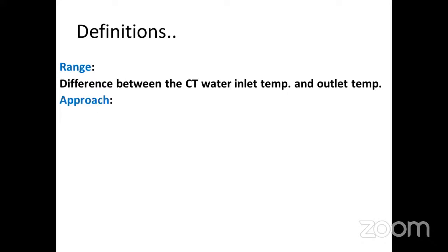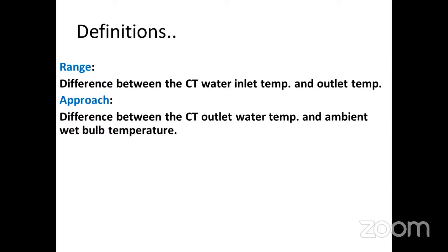Approach. What is that approach? This is the difference between cooling water outlet temperature and ambient wet bulb temperature. Actually, this will be in the order of 6 or 7 degrees centigrade, sir. More than 4 degrees centigrade. If you want to reduce it further, we need to design the cooling tower to an enormous size. But that will be costlier and a huge investment we may be required. So we limit to a certain degree of approach.